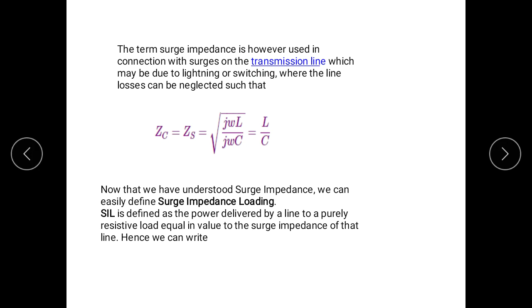Now that we have understood surge impedance, we can easily define surge impedance loading. SIL is defined as the power delivered by a line to a purely resistive load equal in value to the surge impedance of that line. Hence we can write SIL is equal to root 3 VR square upon root 3 Zs, that is equal to VR square upon Zs, or VR square into under root C upon L. The unit of SIL is watt or megawatt.